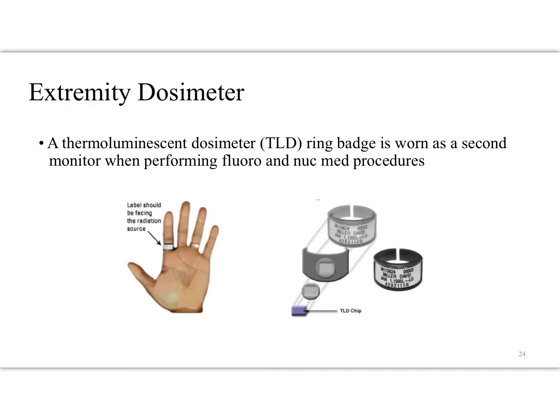Extremity dosimetry is generally done using a thermoluminescent dosimeter, or TLD. This has a special crystal inside that, when exposed to radiation, changes its crystal structure and can be read out by heat. We heat it up, it gives off light, and that is plotted against a glow curve to determine what type of radiation dose was received by the extremity. We like these because they're kind of rough and tumble — if the hand is moving around a lot and getting bumped, it's not going to affect the sensitivity of the device.